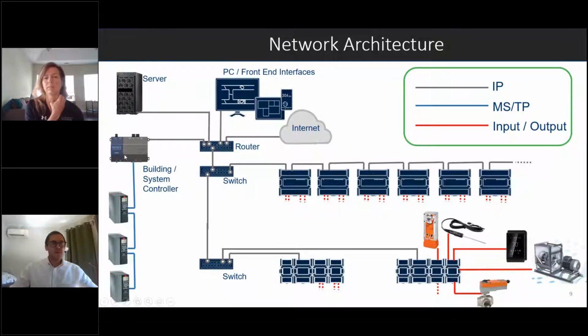We have everything networked together over IP in one consistent system. If you do have other devices that are MSTP, you can still most definitely have a system that doesn't have to be all IP or all MSTP — you can have a kind of mixed architecture. As you can see, we're picking up some VFDs with BACnet over MSTP here, since VFDs are starting to adopt BACnet over IP, but I don't think all manufacturers have gotten that consistently across the board yet. So it's good to know you can put these technologies together that way.